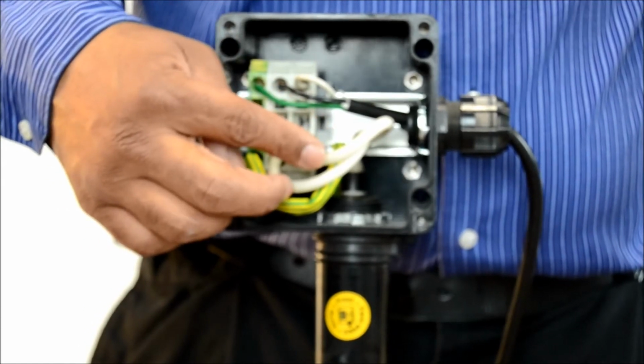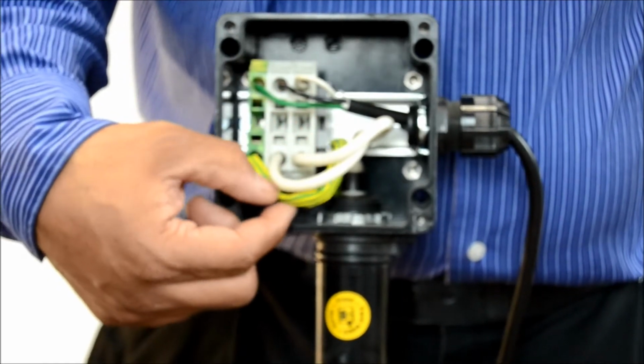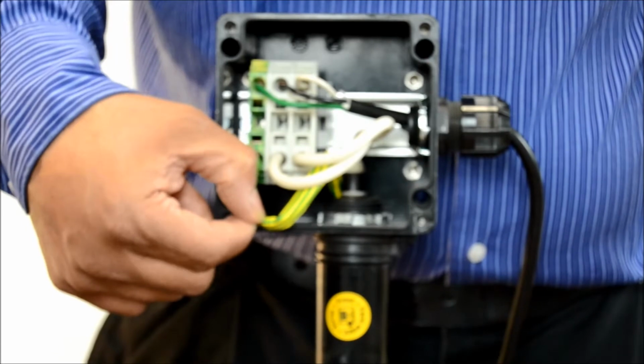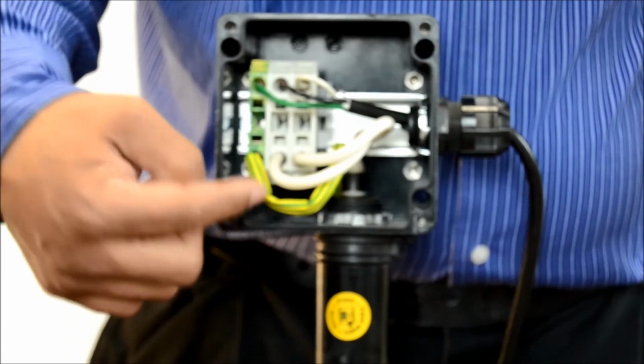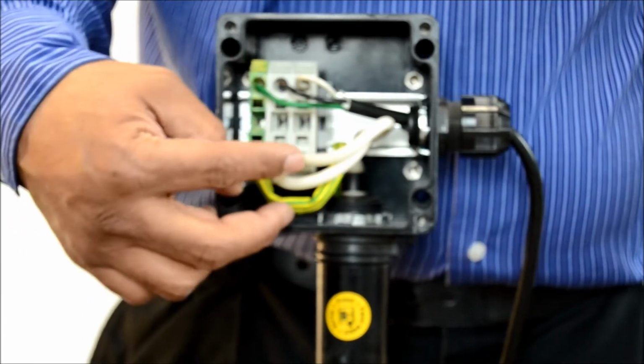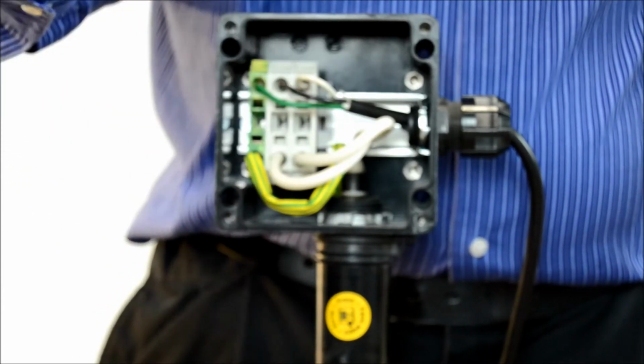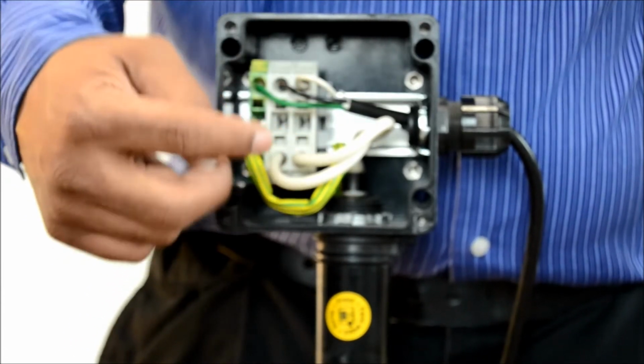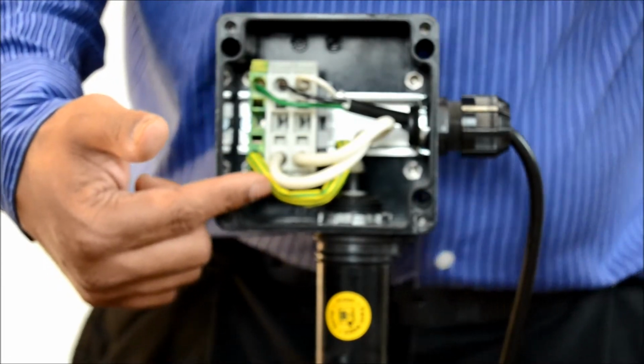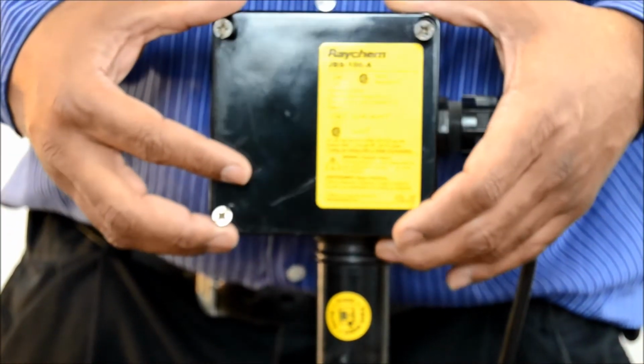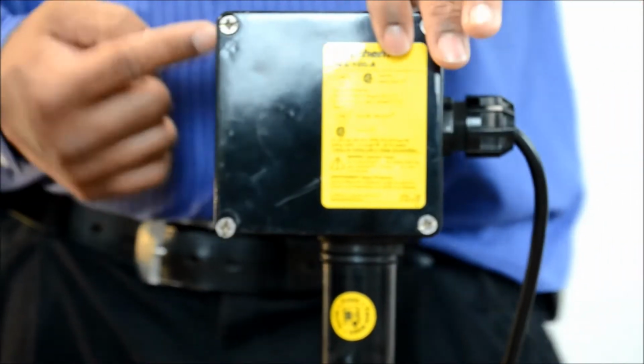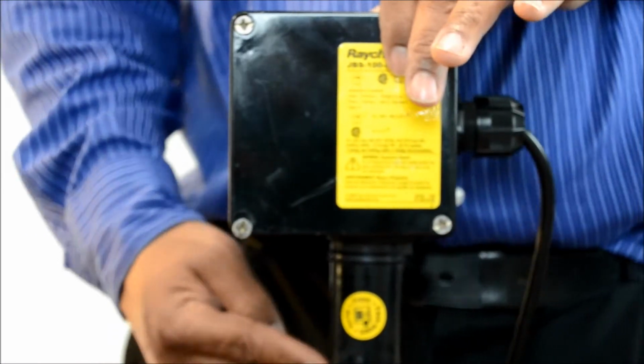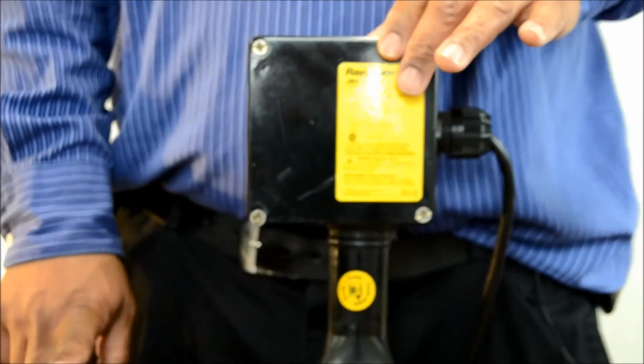One is moisture, and the second is so this doesn't ground fault. Because if these wires weren't here, or this core seal wasn't here, this would probably show up if you tested it as a bad heat trace cable, or it could show up as a ground fault. So this is what you have on site here. Now the heat trace comes out of this box onto the pipe.